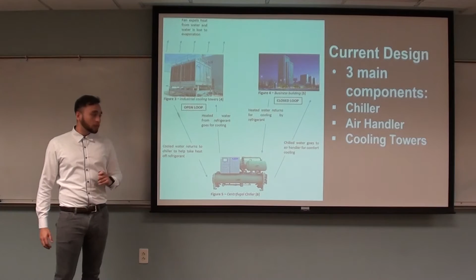Scale and corrosion are the biggest problems that the chiller experiences because calcium carbonate, which is scale, builds up on the wall of the chiller and inhibits the heat transfer surface when the refrigerant comes in contact with it. This means that the chiller has to work X amount of times as hard to produce cold water, thus drawing up more power and increasing your operation costs. The proposed design to improve this issue is to create condenser tubes that are scale and corrosion resistant.